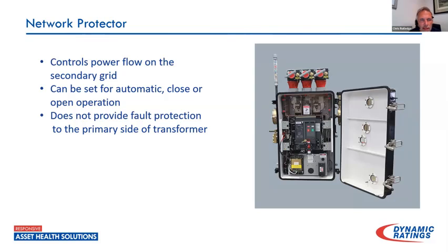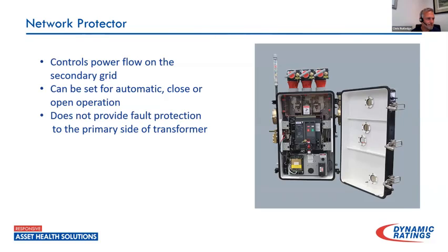The protector is on the other end of this and really doesn't provide any protection to the primary side of the transformer. It's there more or less to put the transformer in service and pull it out of service. If you're looking at the secondary grid and need more power, the transformer will engage; if we start seeing backfeed through that transformer, the protector automatically takes it out. So it's really more of an operations device than a protection device for the transformer — it's a protector for the customer more than the equipment.